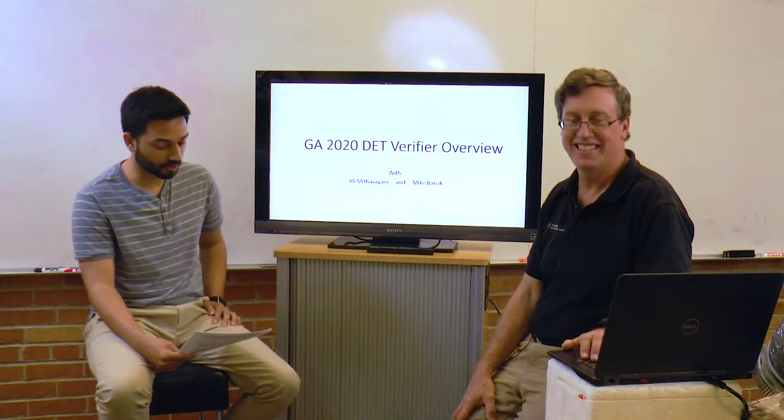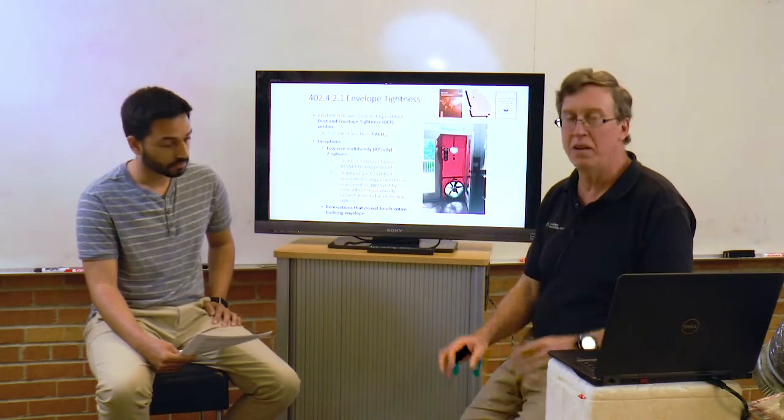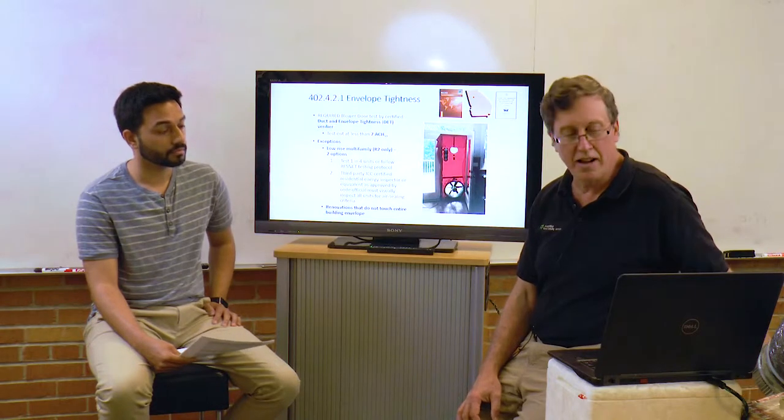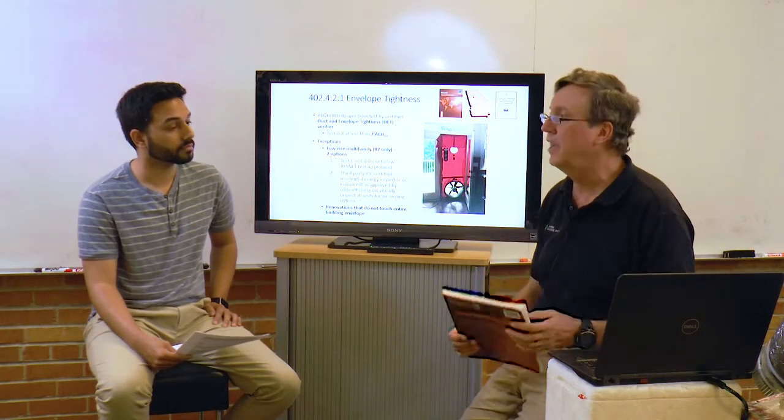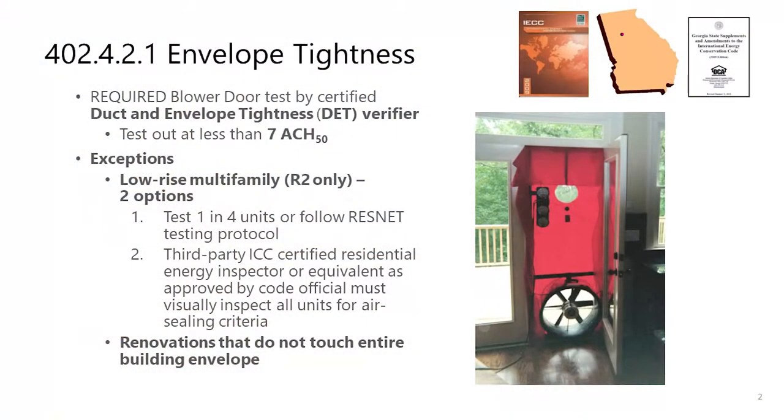Thanks, Mike. Can you give us a quick overview of the 2019 requirements of Georgia? Yeah, so our current code, or I say current, the code that's been in effect in Georgia since 2011 and through the end of 2019 is based on the 2009 IECC with Georgia supplements and amendments. And basically, from a blower door standpoint, the simple answer is single family homes need to come in at less than 7 ACH 50. And I'll add that multifamily is in there as an option. Most low-rise multifamily that's three stories and under does not typically blower door test for code compliance. They have a visual inspection option.